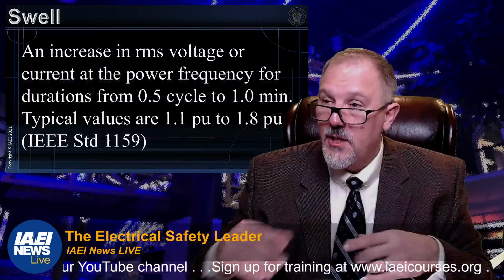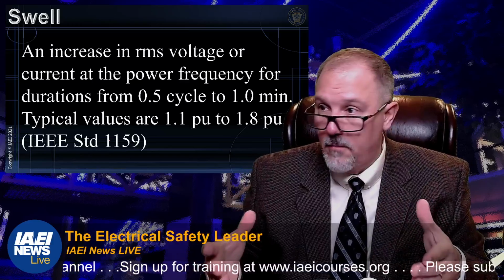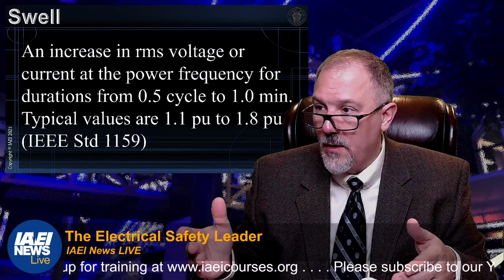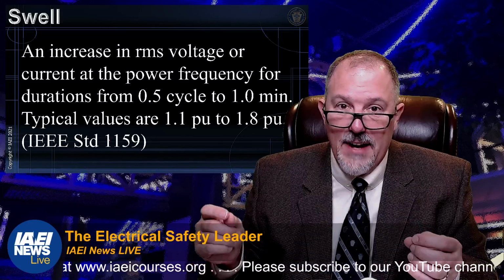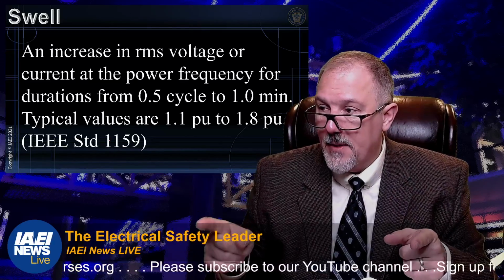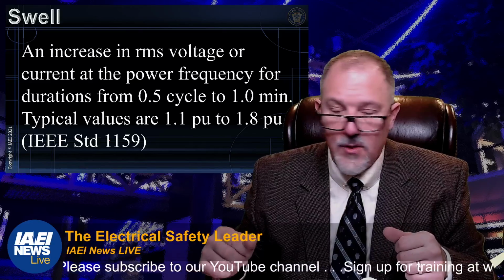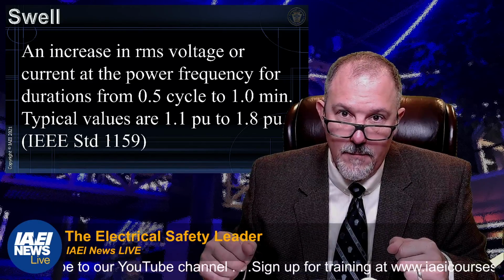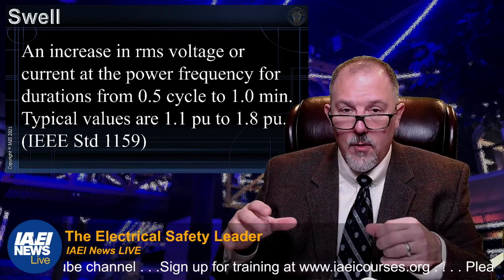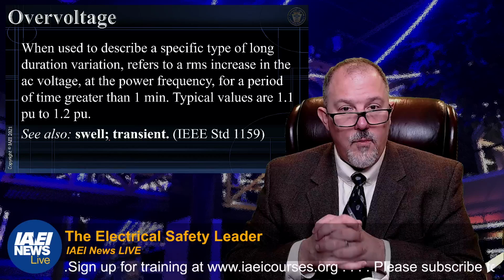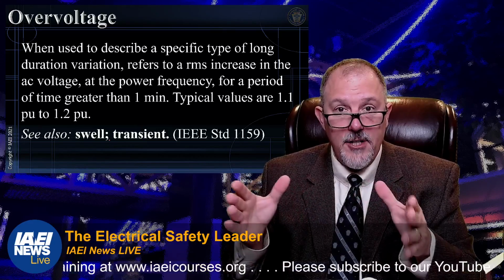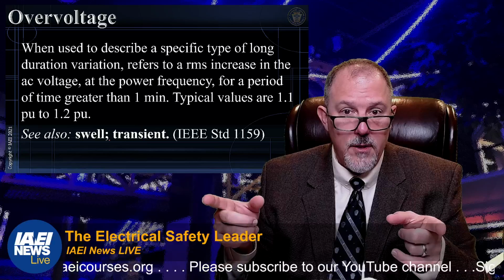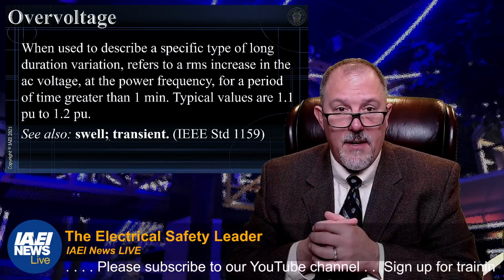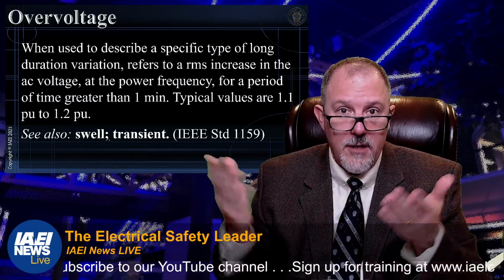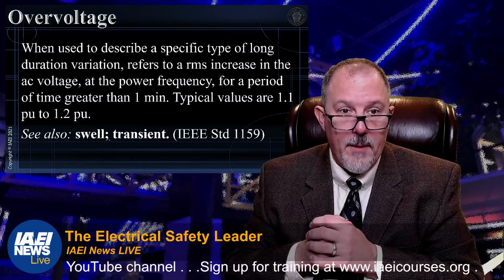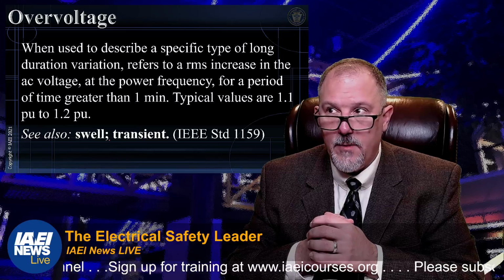Let's talk a little bit more. Swell. What's a voltage swell? This is another formal term. It's an increase in RMS voltage or current at the power frequency for durations from 0.5 cycles, a half cycle, to 1 minute. Typical values are 1.1 per unit to 1.8 per unit. So now we're talking cycles. Remember, with an overvoltage, we have RMS voltage changes. RMS, root mean square, means I need multiple cycles. And this is how IEEE defines it, not how the NEC defines it. So if you're an electrical engineer, this is how you were taught. For a period of time greater than 1 minute, that is what we call an overvoltage.